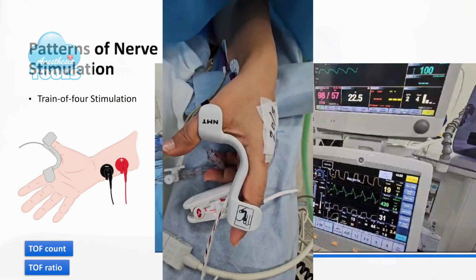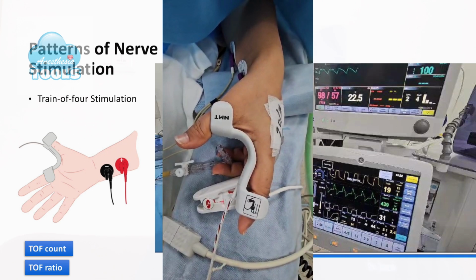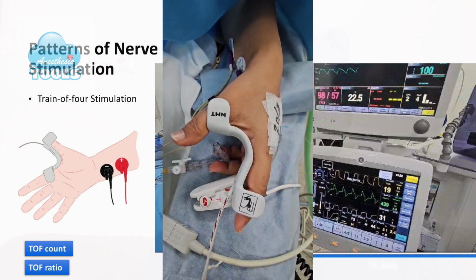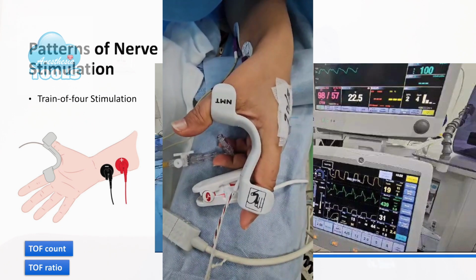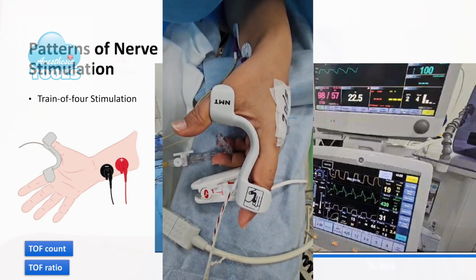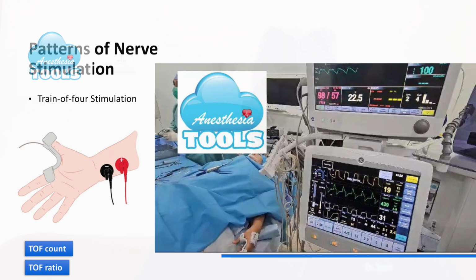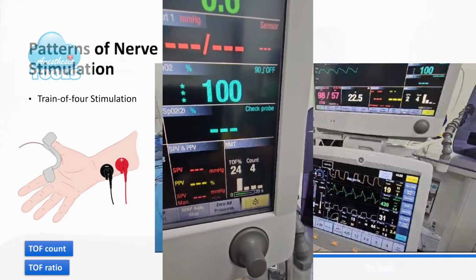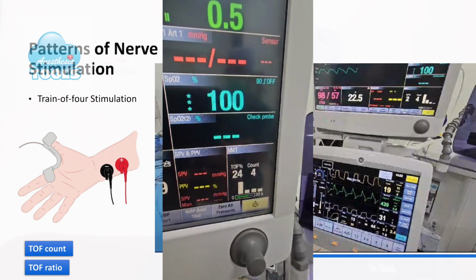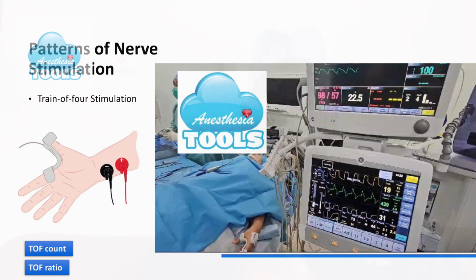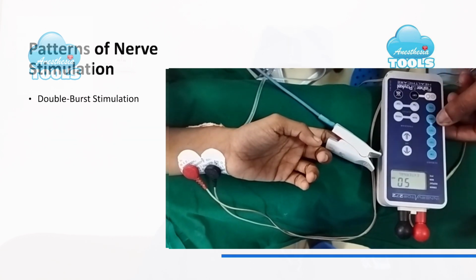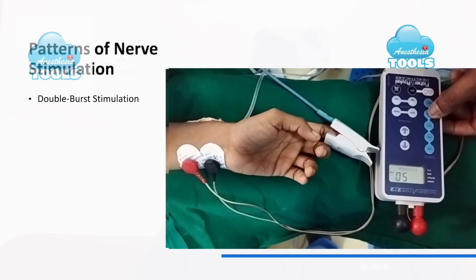In the present day devices, we have quantitative TOF monitoring. In the picture, in the exposed hand, you can see the electrodes for train-of-four stimulation, and there is a mechanosensor between the thumb and the index finger, which will sense the mechanical response. And you can see on the top right corner, the responses are plotted graphically. So now it is very easy and more objective to say that there are four responses, and the monitor will also give you the TOF ratio as well. So here we can see a video of DBS. Now you can appreciate how much amplified the response is.